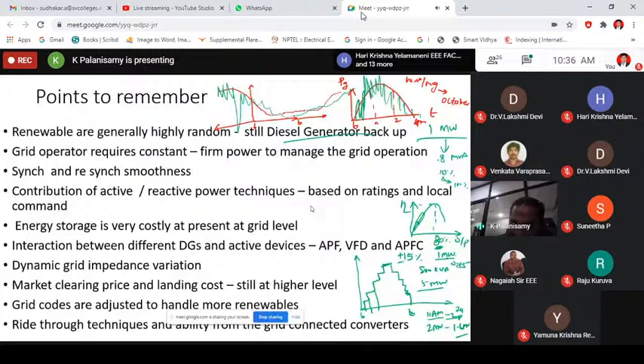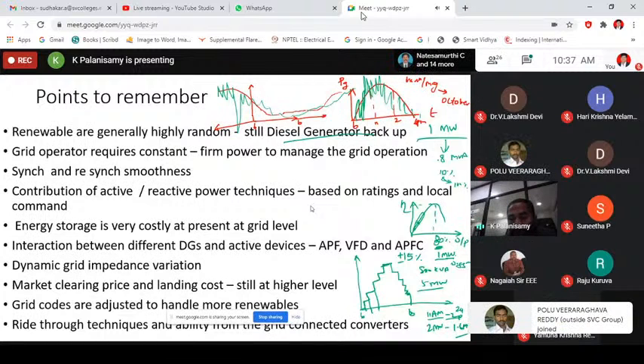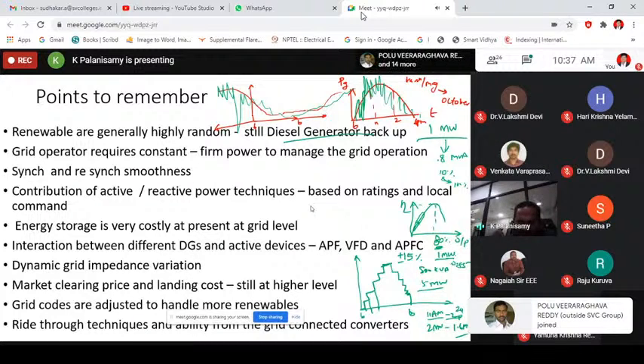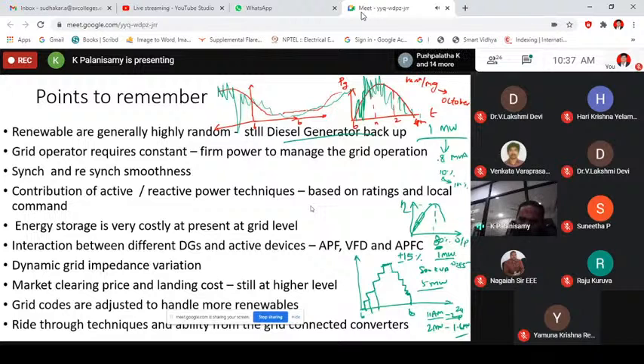So when the frequency varies in the grid, what will happen? The conventional synchronous generator, of course, has kinetic energy because it has a huge rotating mass, so from that it will manage. But grid-connected, power electronics based inverters may not have inertia. So what we have to do is adjust our active power injection. We strictly talk about active power. By adjusting the active power, I can help the frequency regulation of the grid, of the microgrid, right?